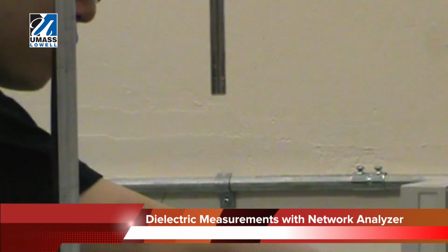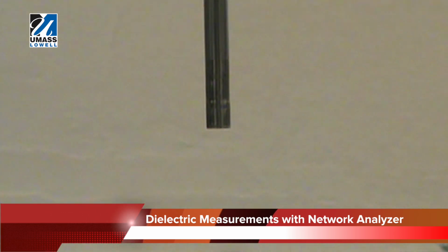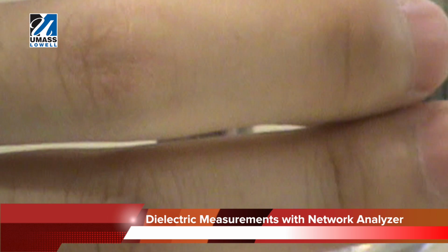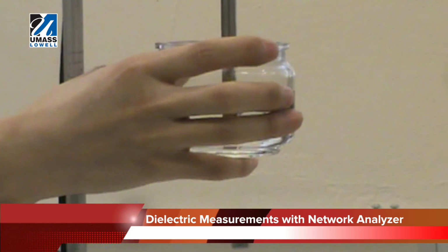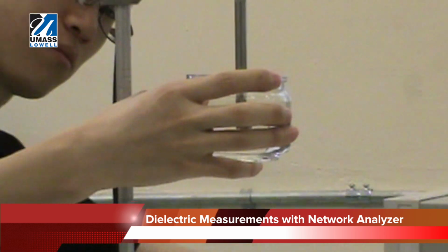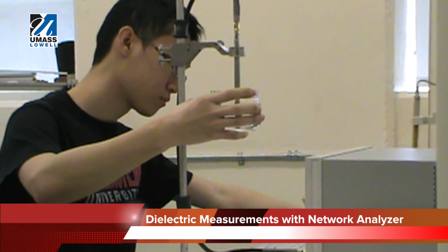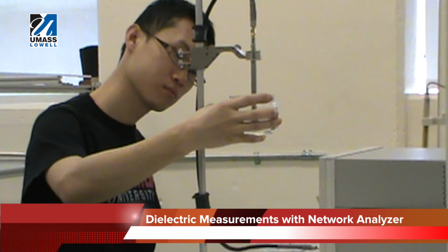The coaxial probe kit that you can see here is an 85070E, which has a frequency range from 500 MHz to 50 GHz. The way that the probe kit operates is that the EM wave penetrates into the material under testing and detects the reflected signal.